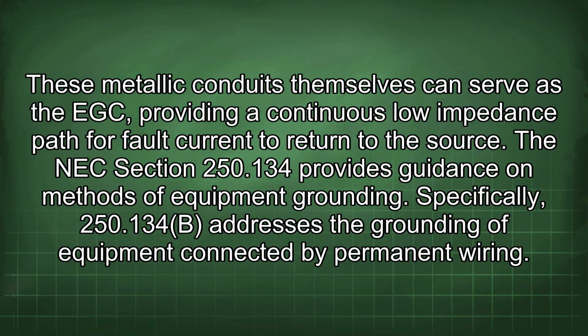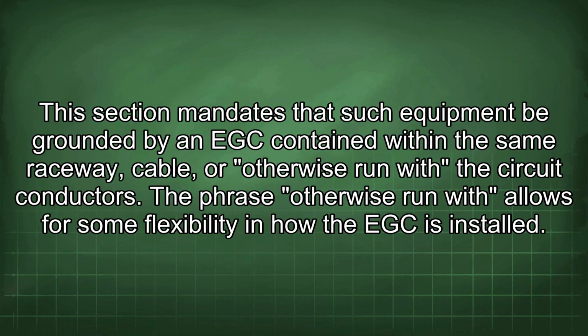The NEC Section 250.134 provides guidance on methods of equipment grounding. Specifically, 250.134(B) addresses the grounding of equipment connected by permanent wiring. This section mandates that such equipment be grounded by an EGC contained within the same raceway, cable, or otherwise run with the circuit conductors. The phrase "otherwise run with" allows for some flexibility in how the EGC is installed.